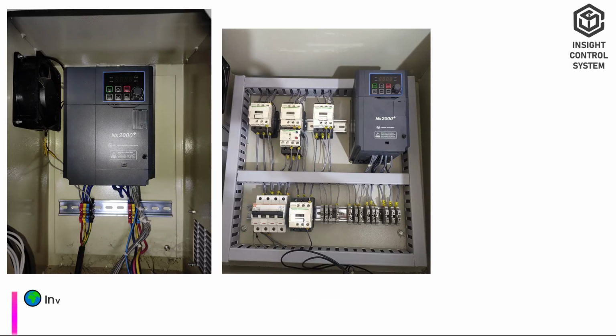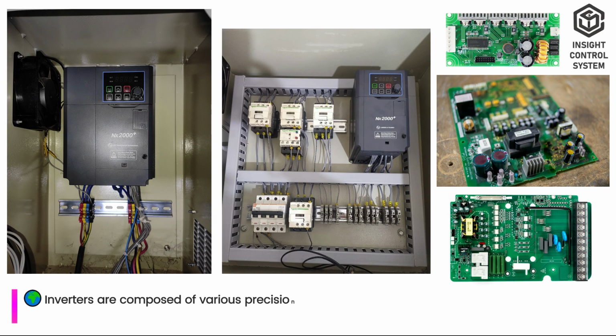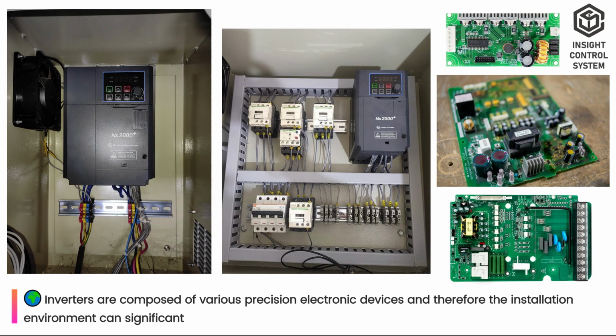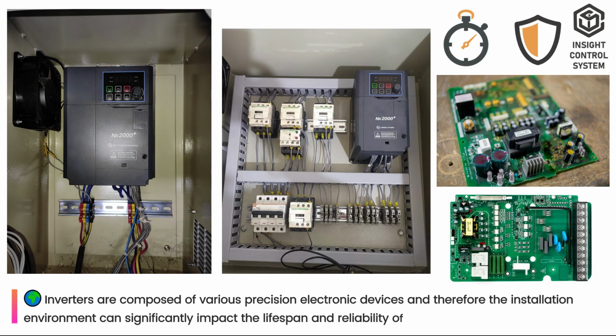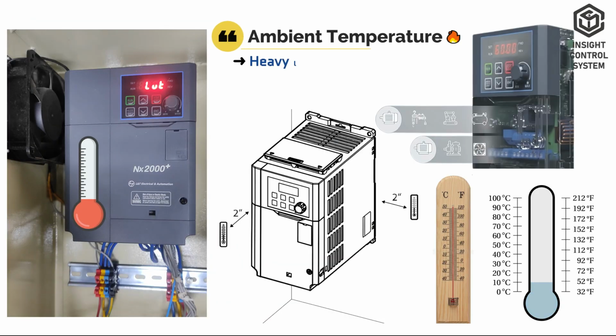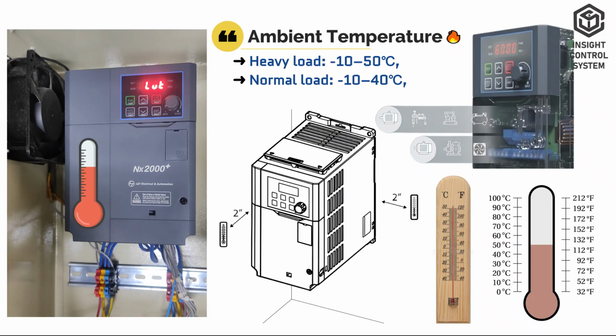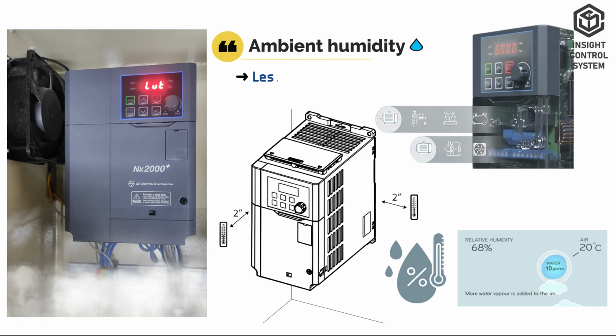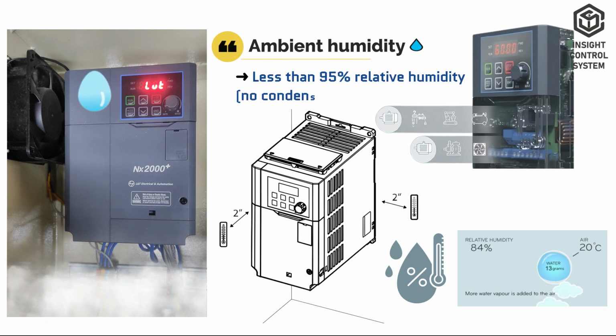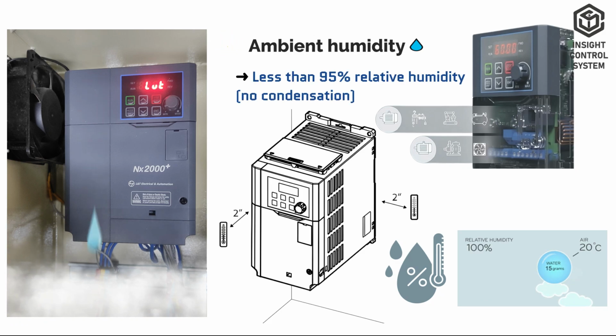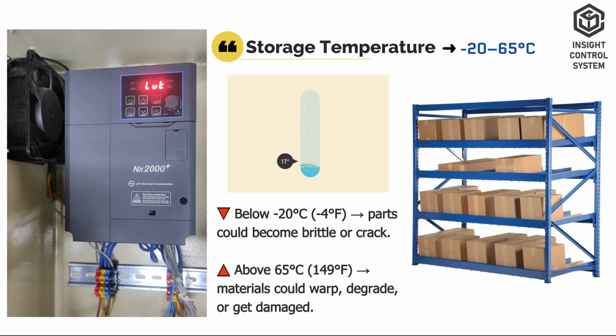Environment data. Inverters are composed of various precision electronic devices, and therefore the installation environment can significantly impact the lifespan and reliability of the product. Ambient temperature. In heavy load is -10 to 50 degrees Celsius. In normal load is -10 to 40 degrees Celsius. Ambient humidity is less than 95% relative humidity. No condensation. Storage temperature is -20 to 65 degrees Celsius.